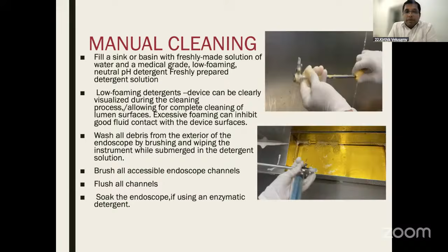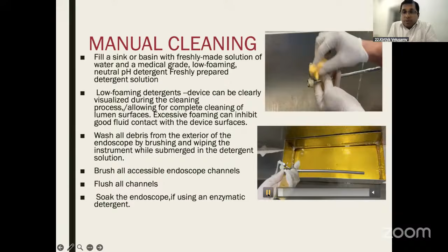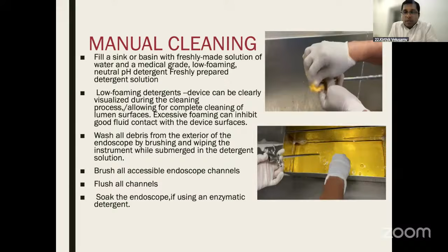We need to wash all the debris as shown in the picture. We tend to wash from the distal to proximal. Every joint and every side channel should be washed. Then we need to brush all the endoscope channels. Then we need to flush with the same solution. Make sure any other dirt elements inside will be washed out. Then this is followed by soaking the endoscope in an enzymatic detergent.